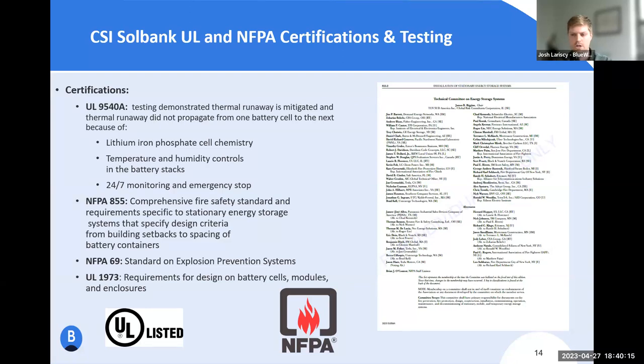There are also a few others worth mentioning: UL 1973, another UL standard for general design on battery cells, and NFPA 69, which looks at standards for explosion prevention systems. This plays into the design features that most lithium ion systems have, in the form of gas ventilation to avoid buildup of potentially flammable gases.